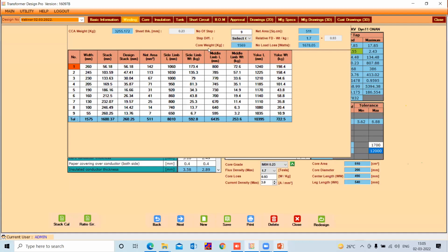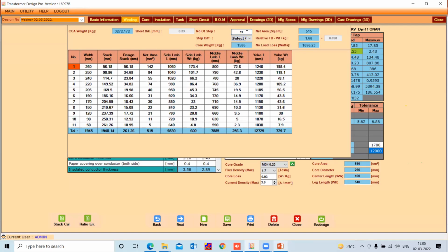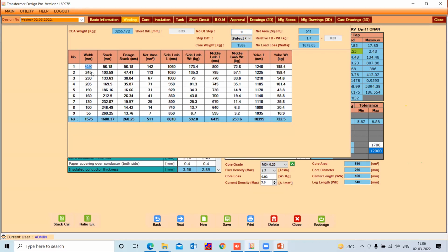You can also see the number of steps here, 0 to 1 to 9. The moment the number of steps you increase or decrease, you can see this particular table getting updated automatically. Now you have changed from 9 to 11. Now automatically the 11 rows get formed and the dimensions related to various stacks come automatically. You can read out the parameters like width, the stack mm, the design stack in millimeters, the net area in millimeter square, the limb, side limb, the side limb weight, the middle limb weight, the yoke length, and the yoke weight. The complete information is available. Let me draw your attention to one aspect in this, friends. Now you see for the serial number 1 stack, 260 mm is the width.